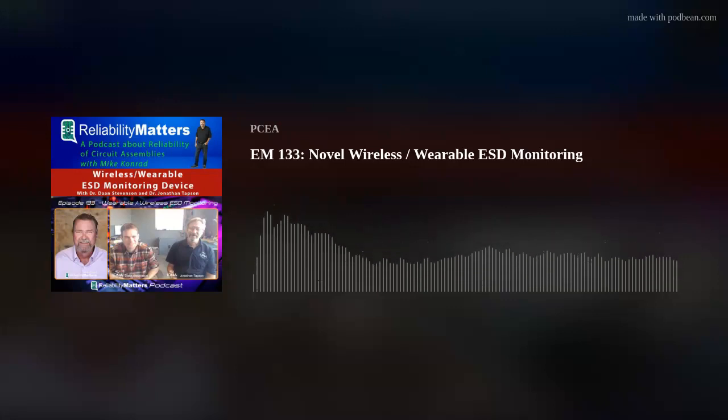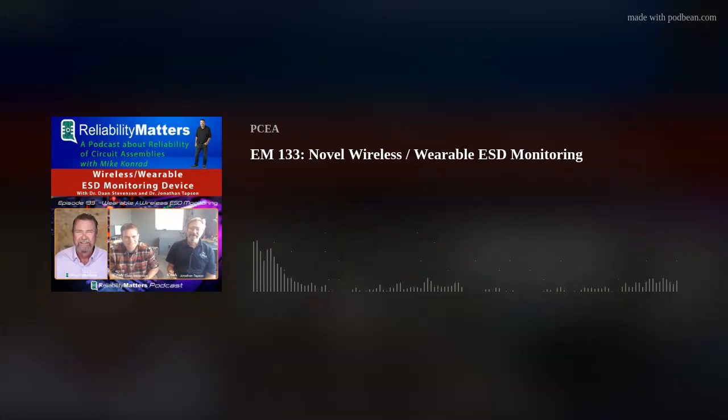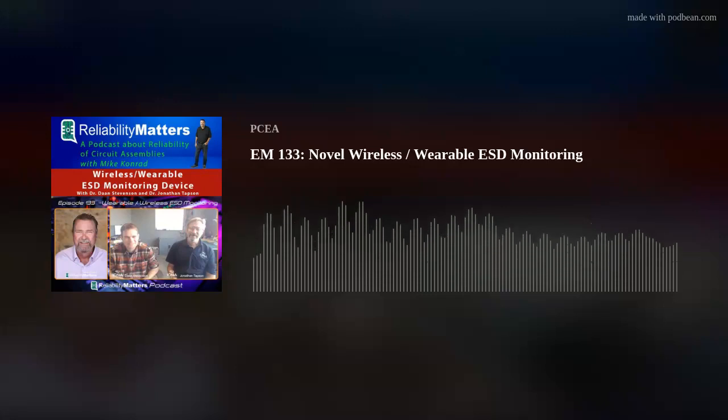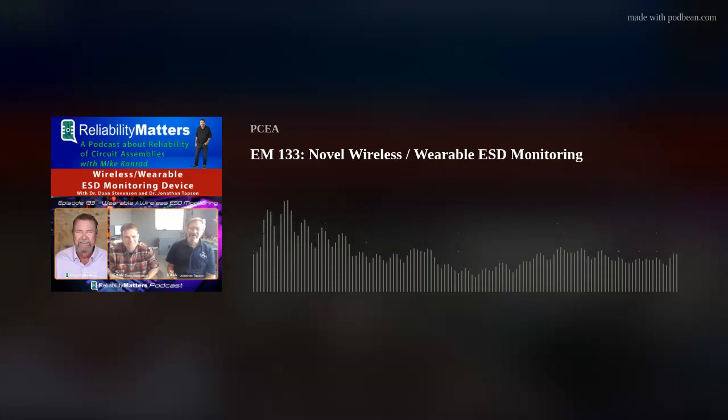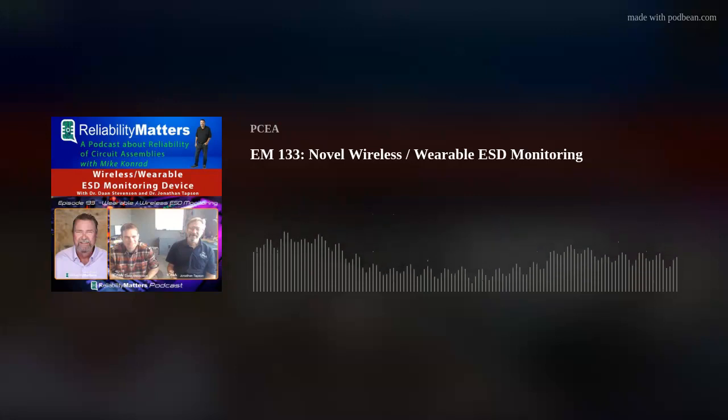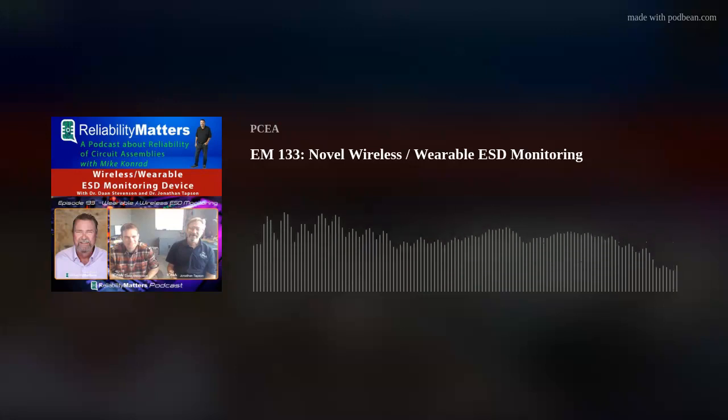What were some of the challenges that you faced when designing this type of product? Yeah, so we spent a lot of time getting this electric field mill to be accurate and free of drift. I mean, that was a real technological hurdle. And we achieved it with persistence and good data collection. Honestly, we've been a data-driven company from the very beginning, and that shows in the product. Collecting the information we needed to make iterative improvements on the sensor design has paid off because of how accurate the device is now, where we can actually measure the body voltage to within 10 volts, which is quite impressive.